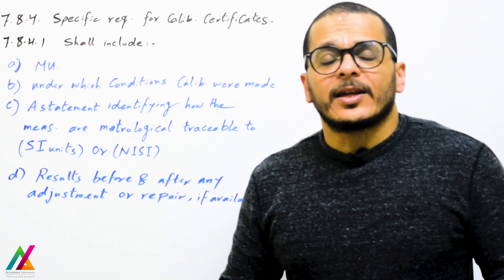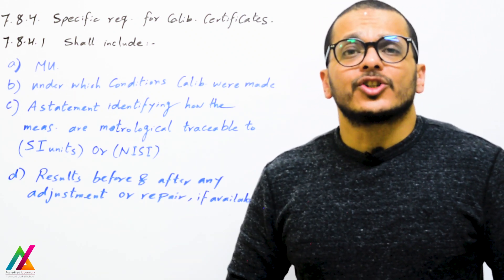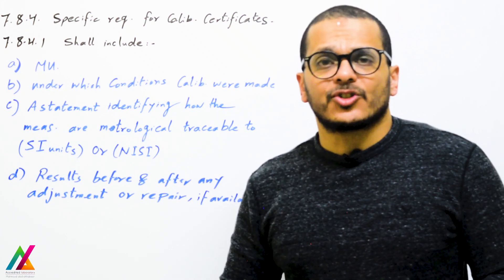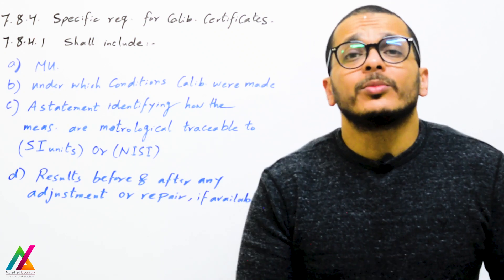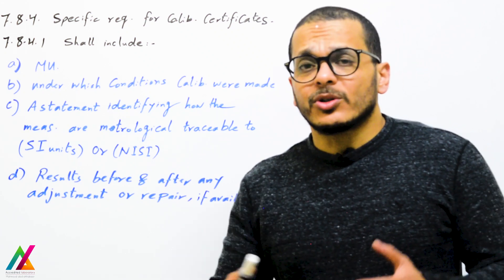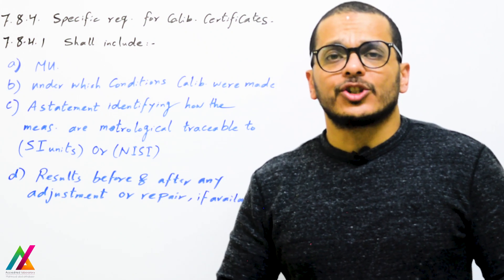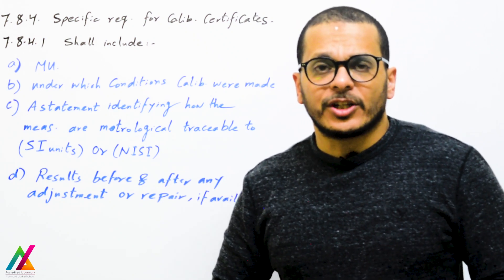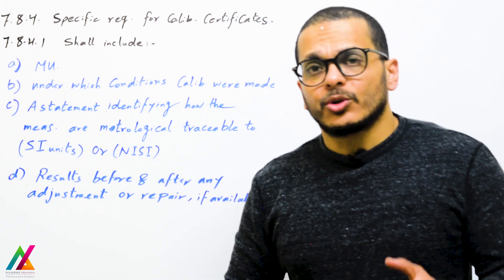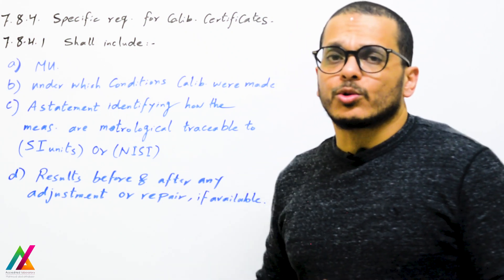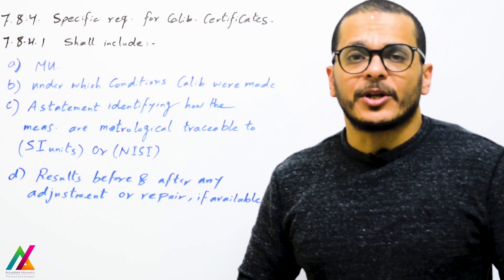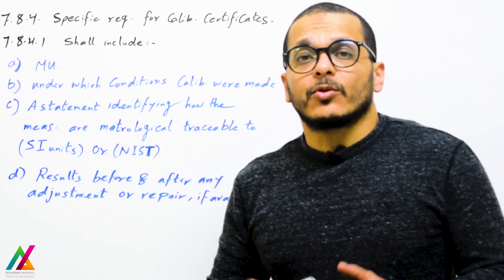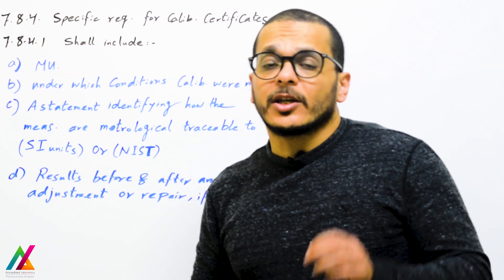Also, the conditions under which calibration was performed shall be included — such as environmental conditions like temperature or humidity — because these conditions may affect the calibration results. This information shall also be included in the calibration certificate.